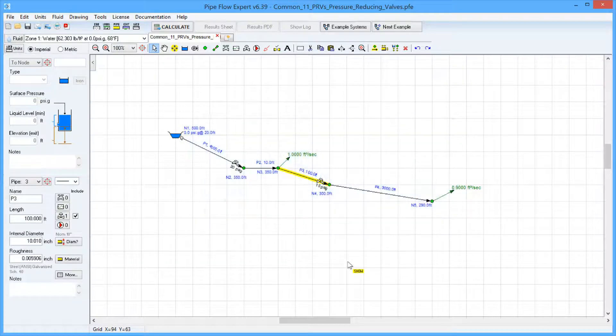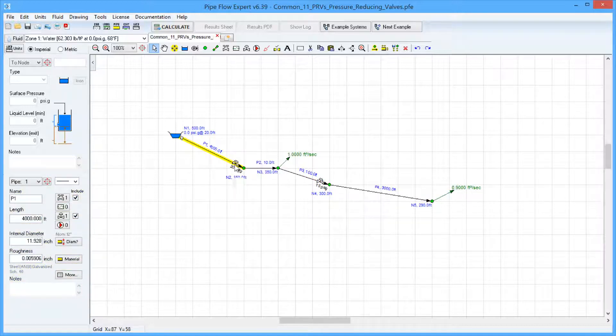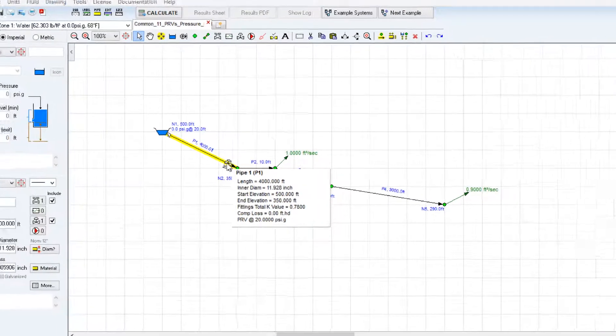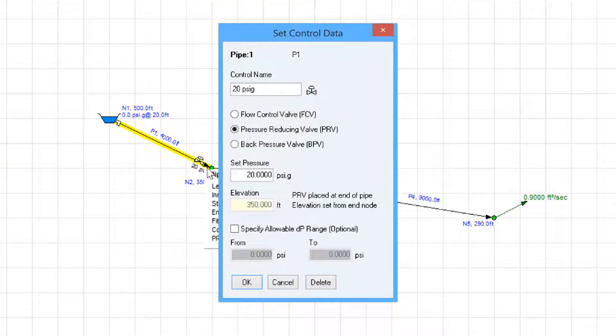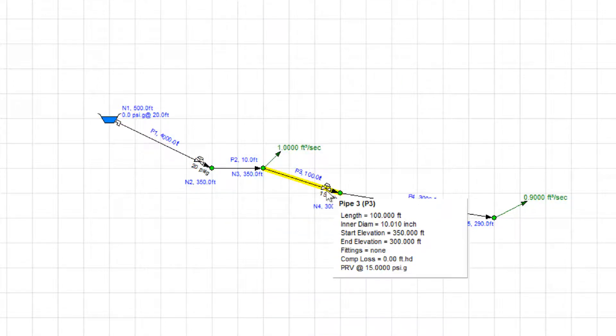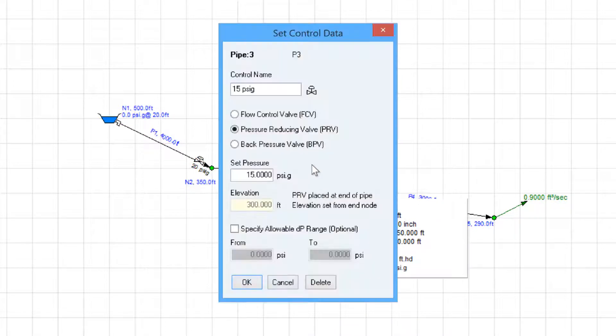Pressure reducing valves are used to limit the pressure in the lower parts of a system. The model on the screen has some pressure reducing valves. Pipe 1 has a pressure reducing valve to reduce the pressure to 20 psi gauge, and pipe 3 has a pressure reducing valve to reduce the pressure to 15 psi gauge.